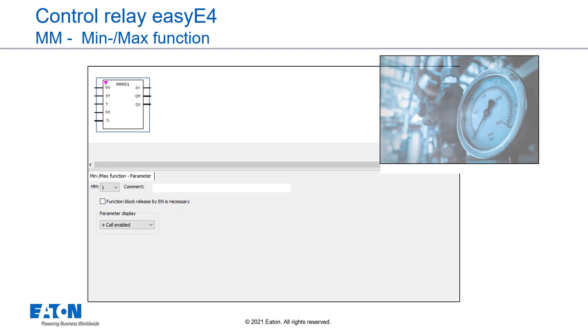At the beginning of the measurement, both values are zero. These can also be reset to zero by the RE, which means reset input. It is possible to perform the calculation cyclically or only by rising edge at the function block trigger input T. The typical application is monitoring a process value cyclically.